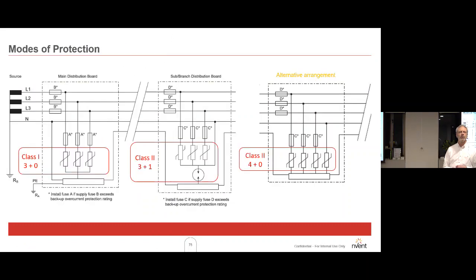Modes of protection. On the left is at your main board where you've got each surge diverter down to your neutral earth bar. At your distribution board, you have those three surge diverters to your neutral, and then another surge diverter down to the neutral earth bar. And you could conceivably put surge diverters from each phase to earth as well, and that's the way it used to be done, but it's been determined that that's not essential and it's not cost effective. And it's an alternative to the middle one. You can have a surge diverter from each phase and from neutral to earth.